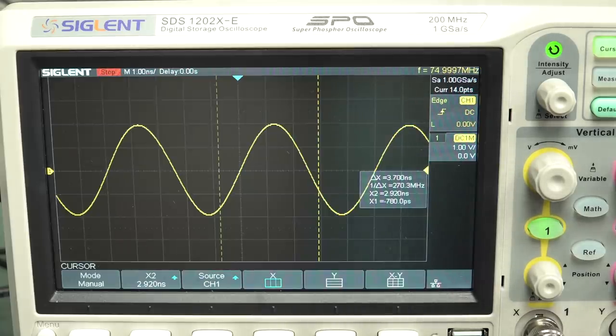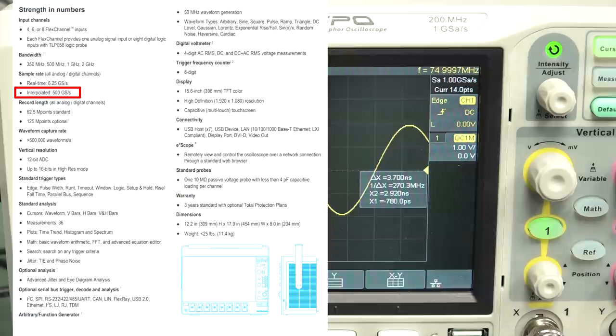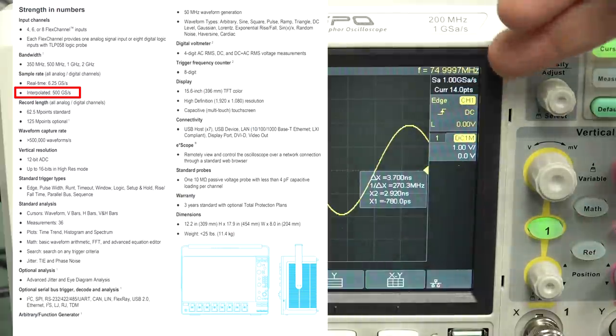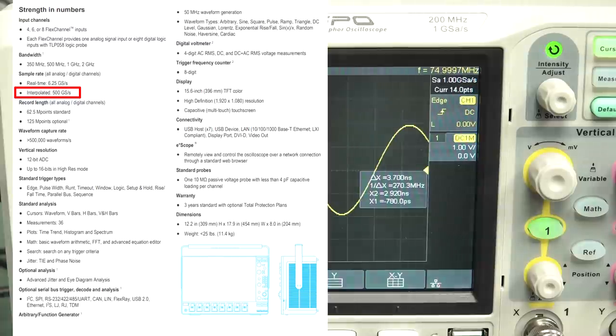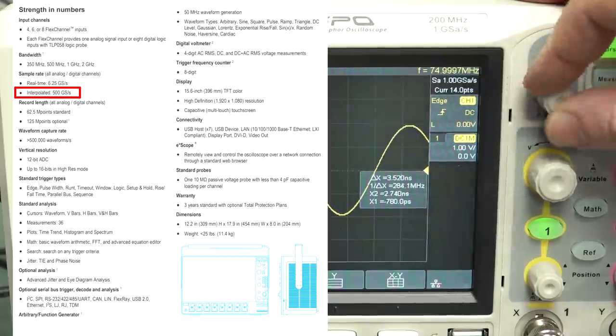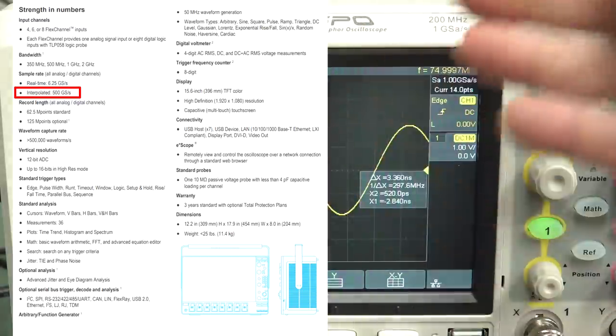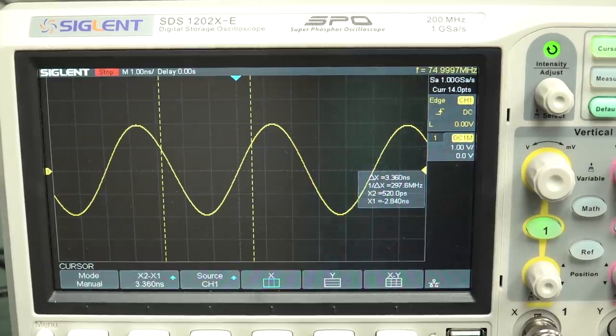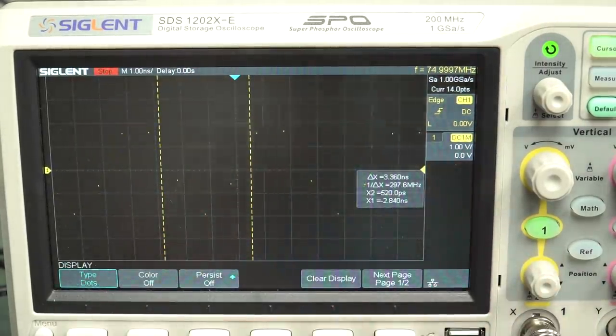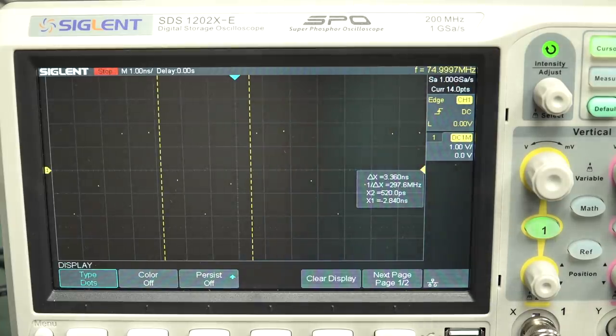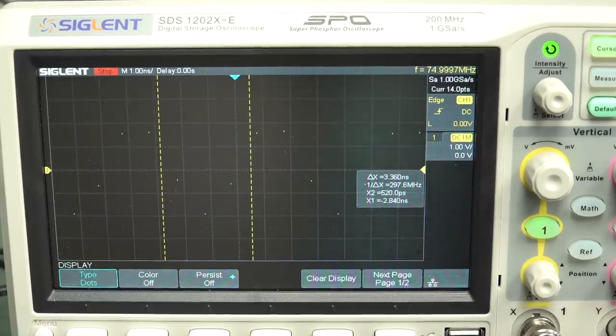Even though we've only got one gig sample per second, when you turn on your interpolation down here, when it's filled in the dots, look, we can go in there and more accurately measure with our cursors a, what's effectively a much higher sample rate. In fact, we can go up in increments here. Look at this, x1, x2 of 20 picosecond steps there. Wow. And if you get your confuser out and do 20 picoseconds, and you invert that on your calculator, what do you get? 50 gig. So we've effectively turned our one gig sample per second sample rate into an effective, I'm going to use the quote marks, effective sample rate of 50 gig samples per second. And particularly on very high-end scopes, you will actually see them advertise this effective, or sometimes called interpolated sample rate, of much higher than what the actual ADC sample rate is. And it can actually be, depending on your input signal, can actually be a very valid, mathematically valid method of recreating your signal and actually measuring it at a higher sample rate.